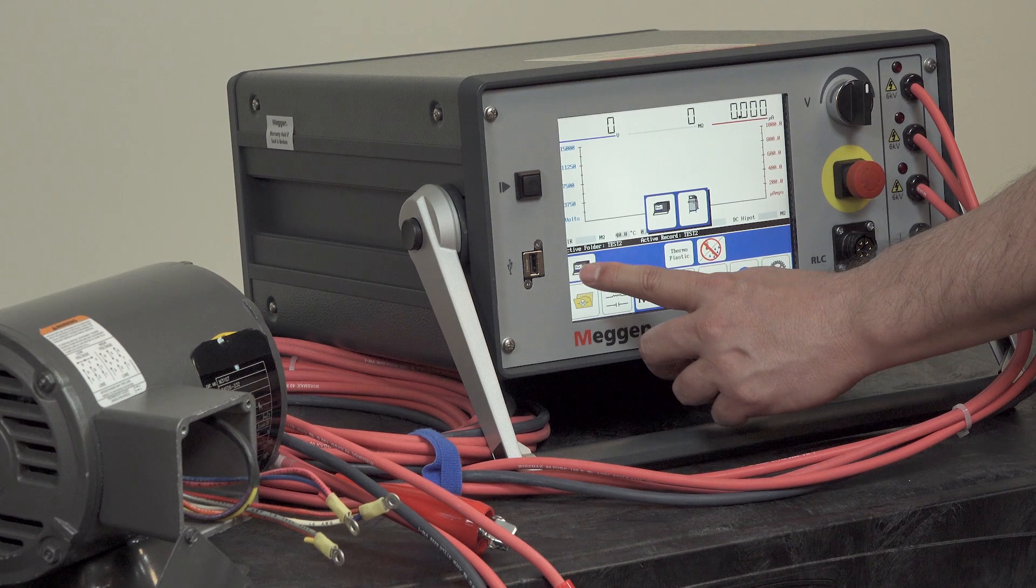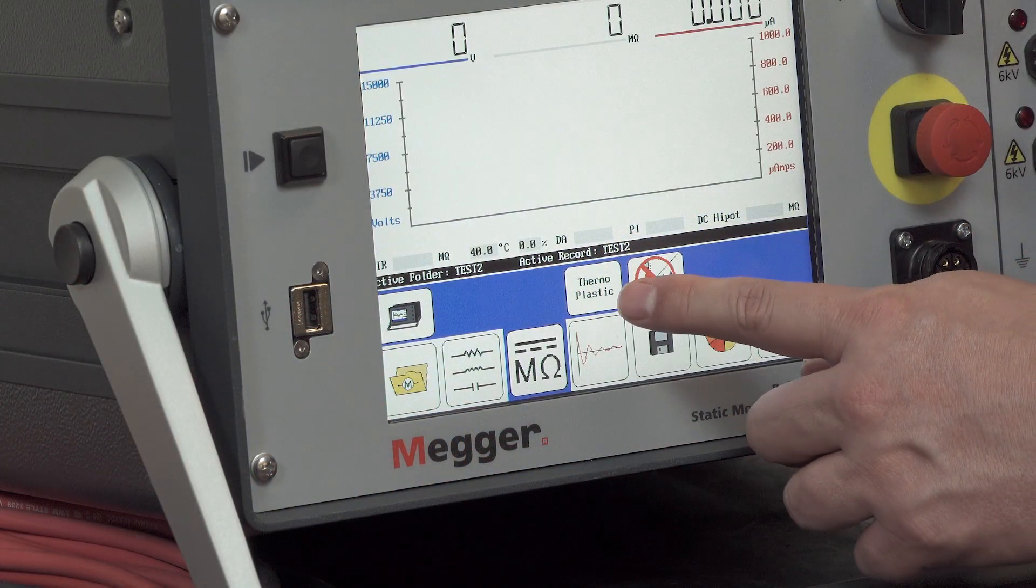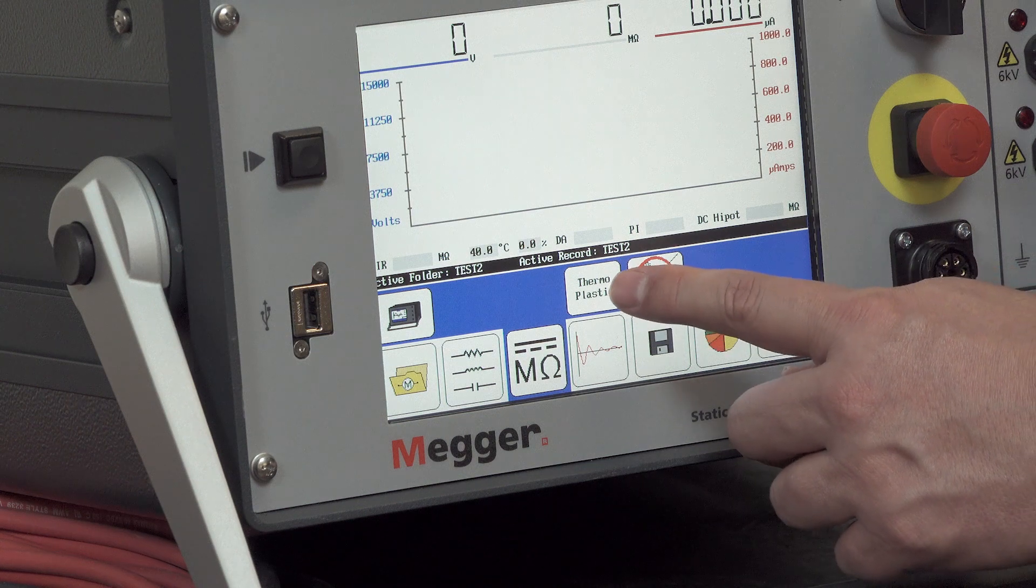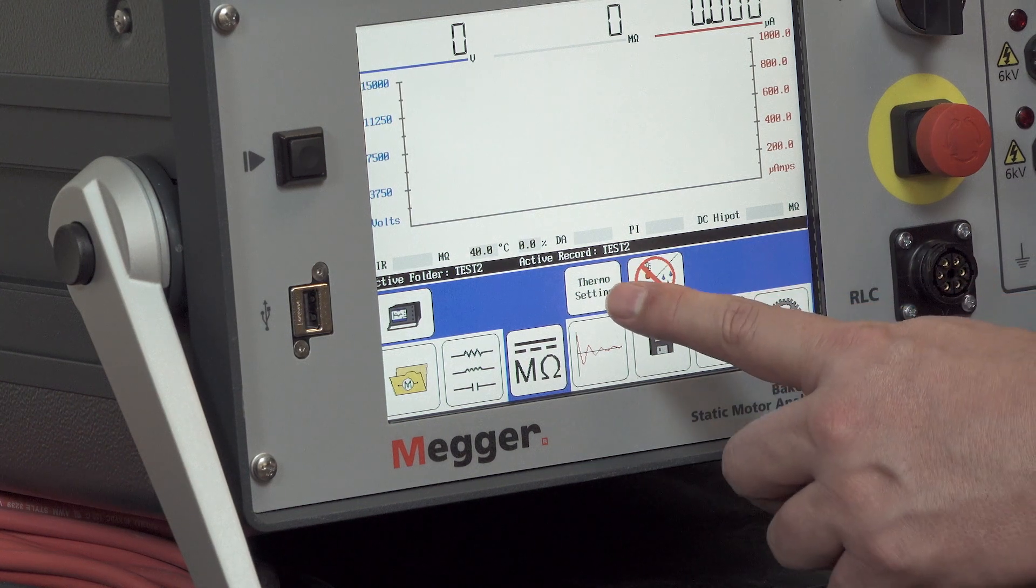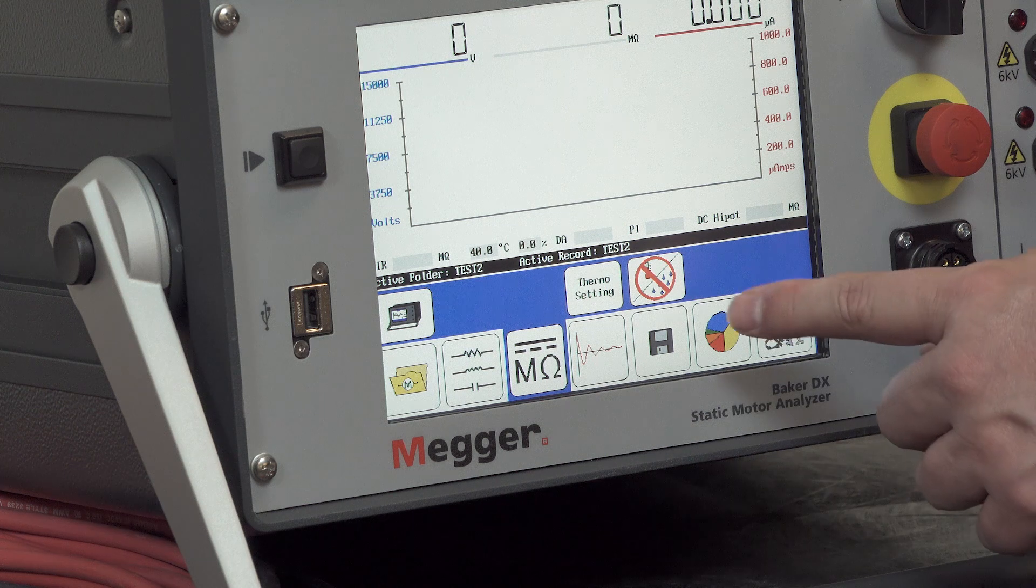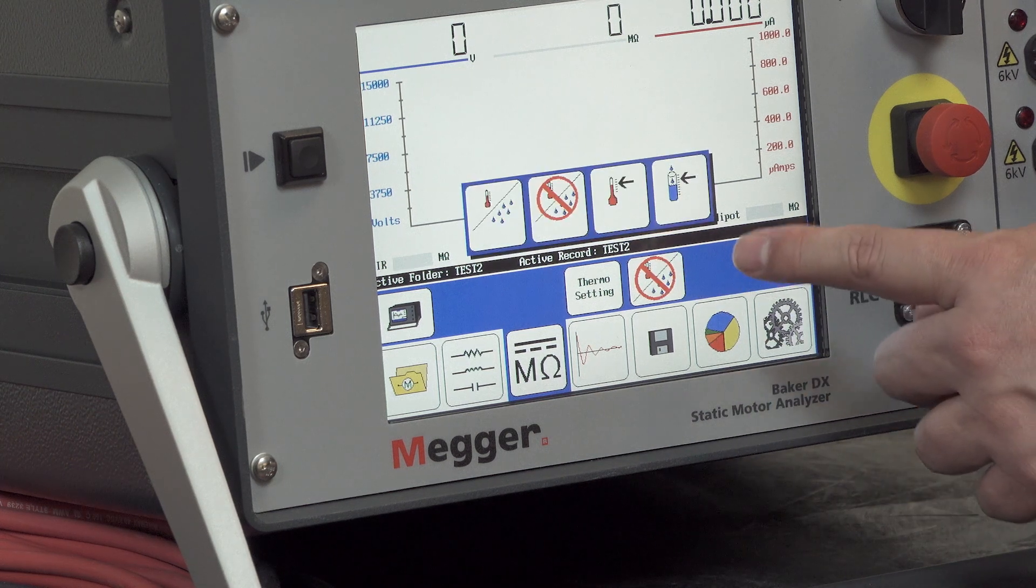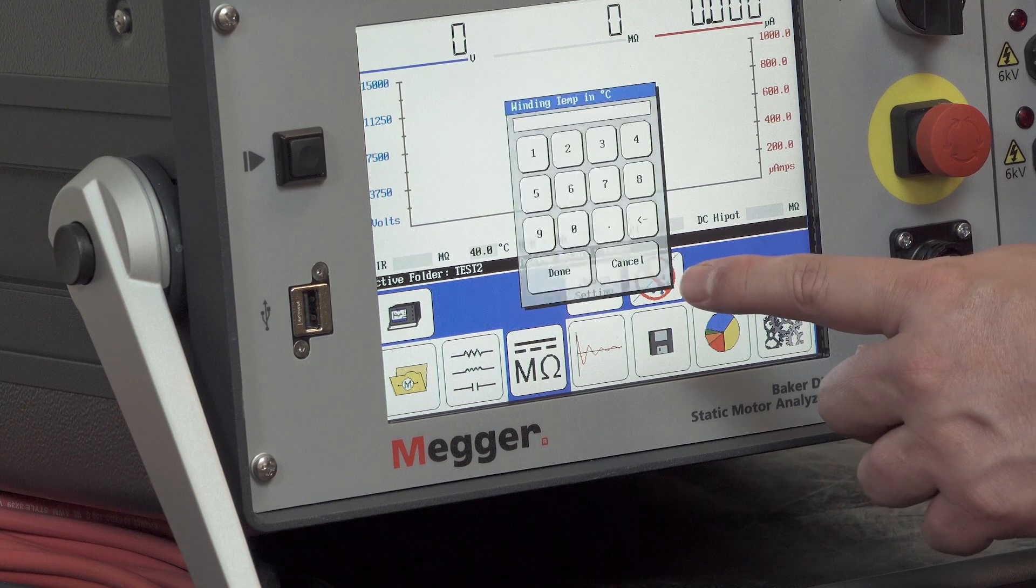Next we'd like to select the proper temperature correction formula for the insulation under test. In this case it's thermosetting insulation, and now I want to establish the temperature correction. I'm going to enter a temperature of the winding, in this case 21 degrees Celsius, done.